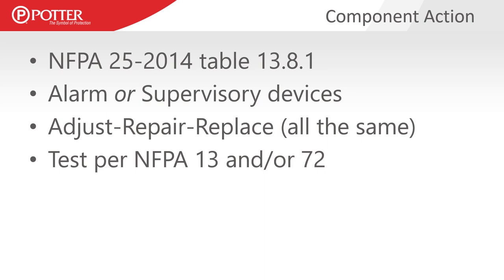NFPA 25 has a component action table — Table 13.8.1 in the 2014 edition — that tells us whenever we make a change to the system, what we have to do to restore it to service. Alarm or supervisory devices are lumped together in that table. It says that if we adjust, repair, or replace any of these devices, they have to be tested per NFPA 13 and/or NFPA 72. Most of the time these acceptance tests line up, but if we replace or adjust one of these switches, there's a complete acceptance test that has to take place per NFPA 25, which then refers us to NFPA 13 or 72 for those acceptance test procedures.